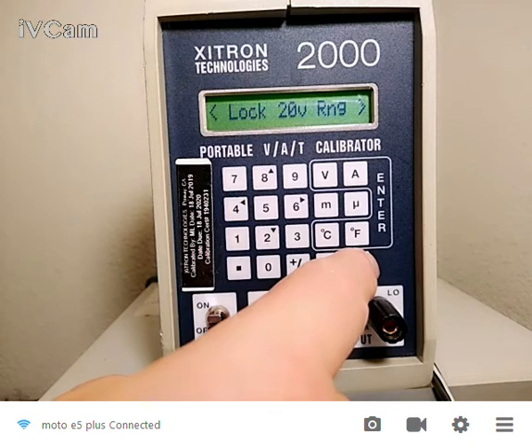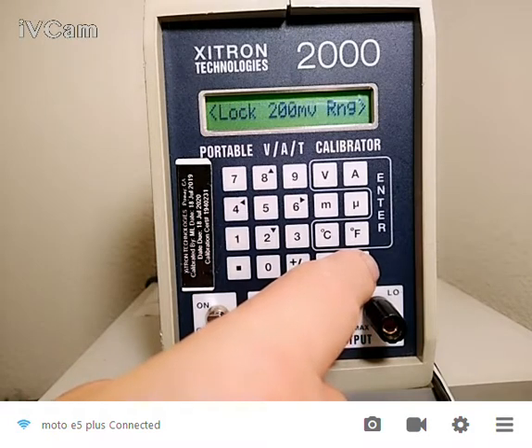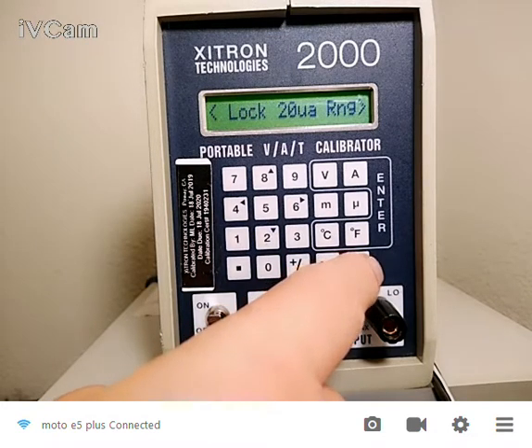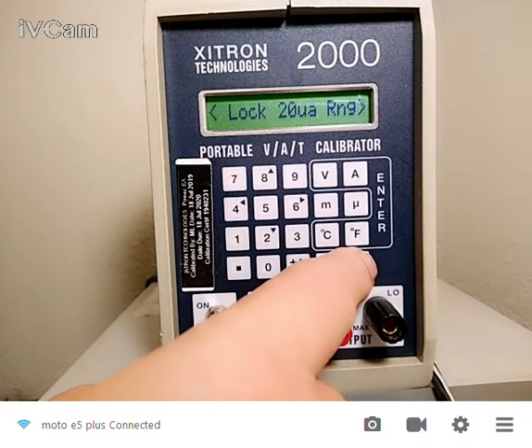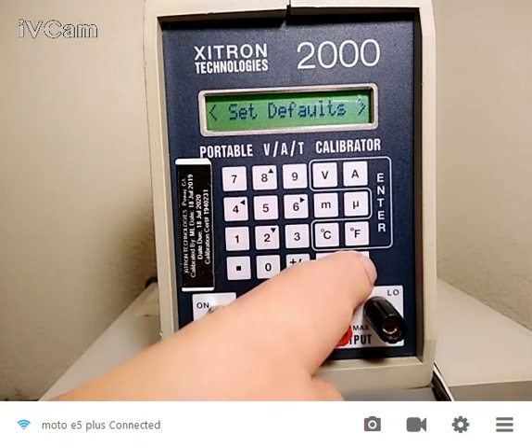And I have quite a few ranges on this instrument. It has a DC 20 volt range, 2 volt, 200 millivolt, and 20 millivolt. In current, it has a 20 milliamp, a 2 milliamp, a 200 microamp, and a 20 microamp range. To prevent it from changing in the middle of a calibration, I can lock that range, and also make sure I don't put out more voltage or current than what I want the instrument to see. So I can adjust my defaults. I'm not going to do that right now.